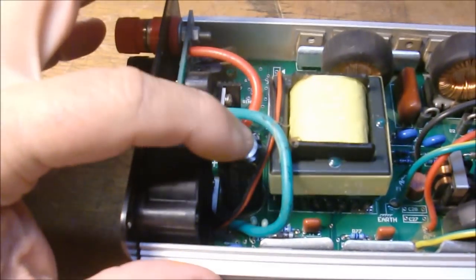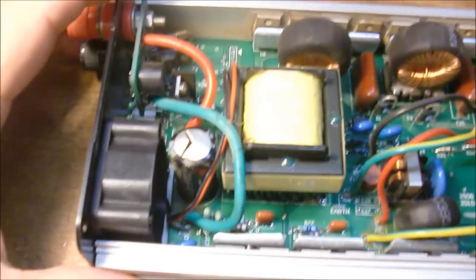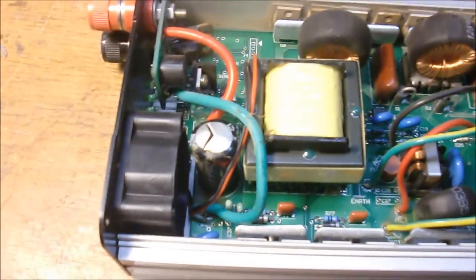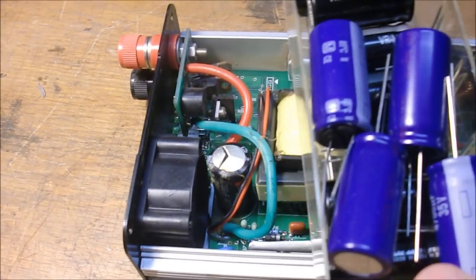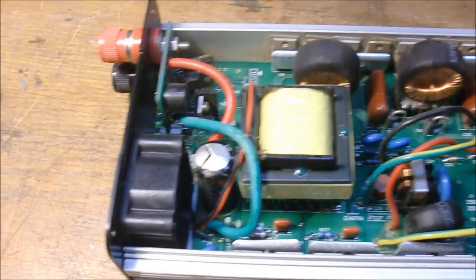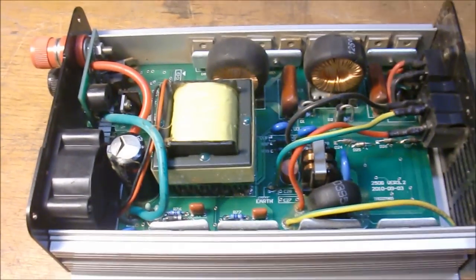There's this large DC capacitor on the DC side that blew its lid. So I'm going to replace that. I actually have a whole supply of those capacitors. And we'll see if we get this thing back going again.